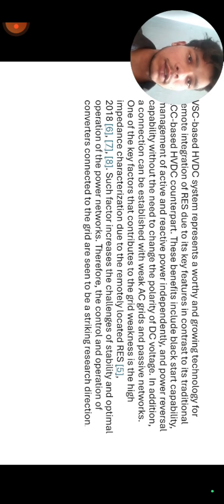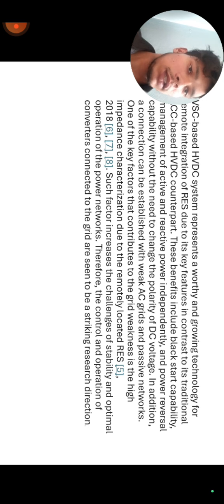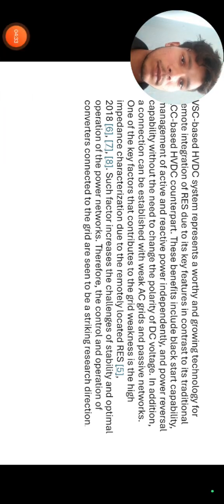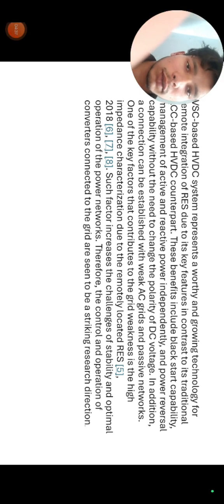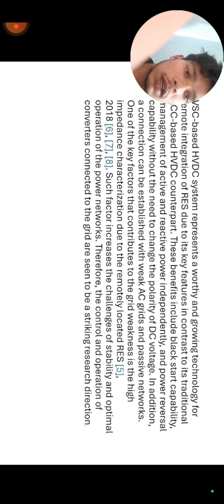One of the key factors that contributes to grid weakness is the high impedance characteristic due to remotely located RES. Such a factor increases the challenges of stability and optimal operation of the power networks. Therefore, the control and operation of converters connected to the grid are seen as a striking research direction.